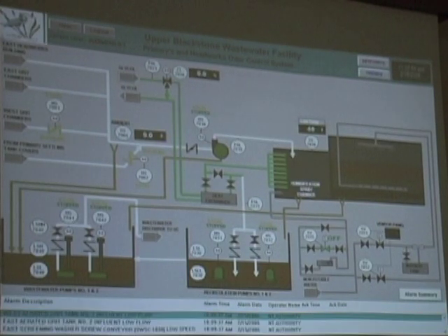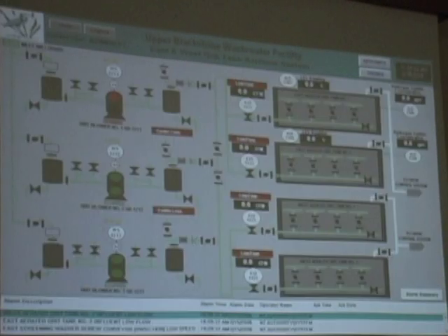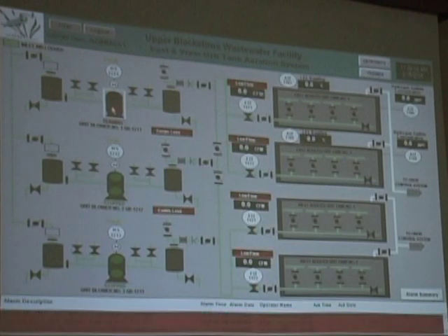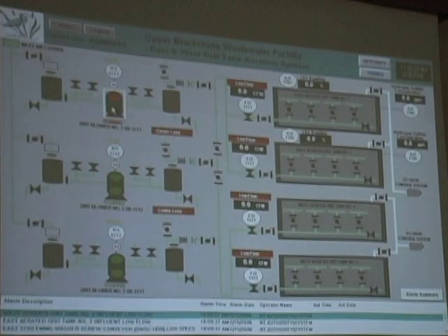So we're looking at this screen right here, the blower screen. Right up on the top, say we're running one blower, well, actually, we'll use number 3 blower because that one's running. We could have a run status, but also have a comm loss. You would, because this is a communication and not a hardwired thing, it's going to leave the data in the last state that it found it. Oh, okay. So right now, that's why it's showing here that grit blower number 1 is running with the comm loss. That was the last communication that it had, was saying that it was running. So you would have to actually go to the drive and make sure that it's running.